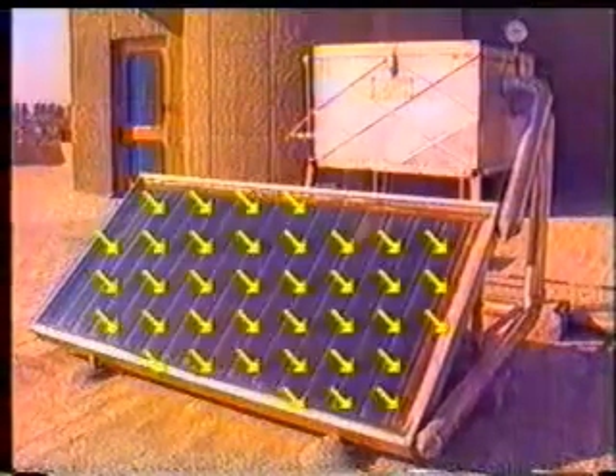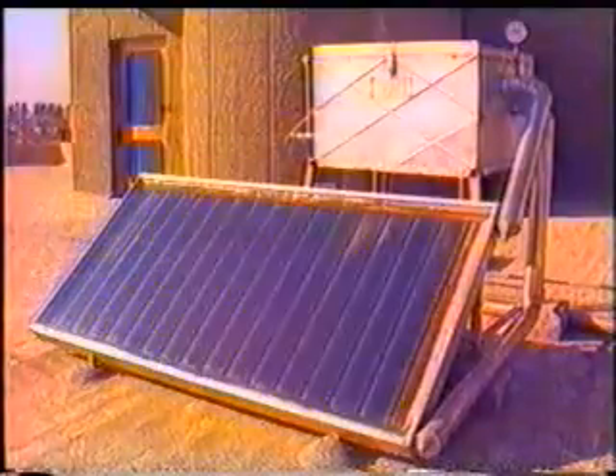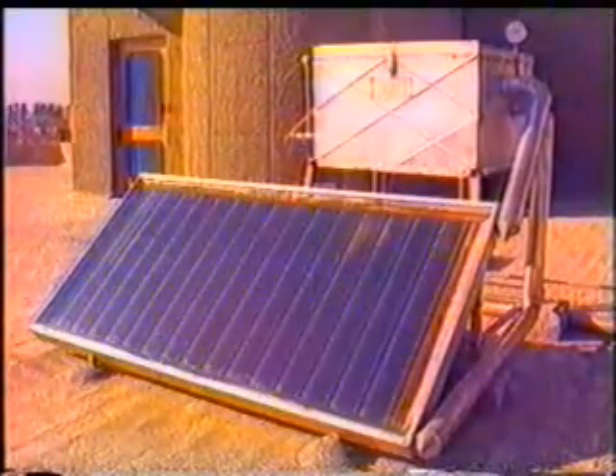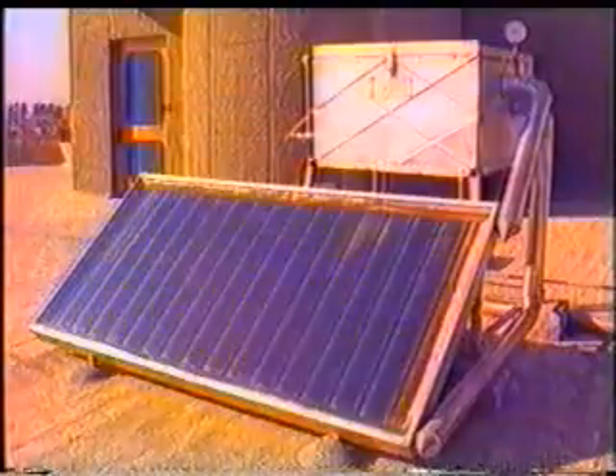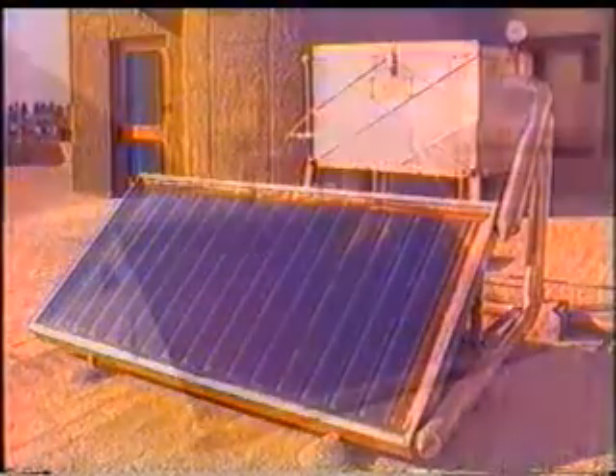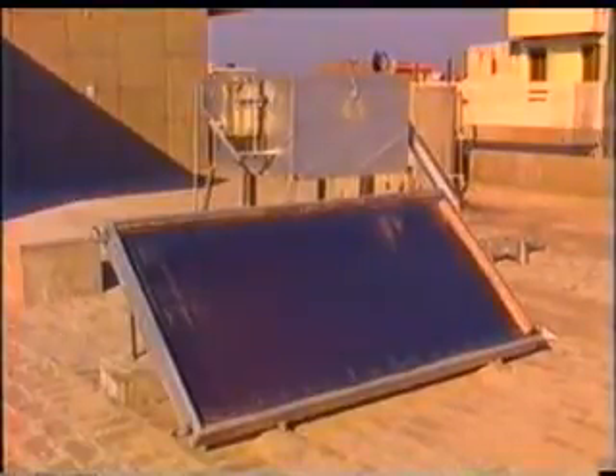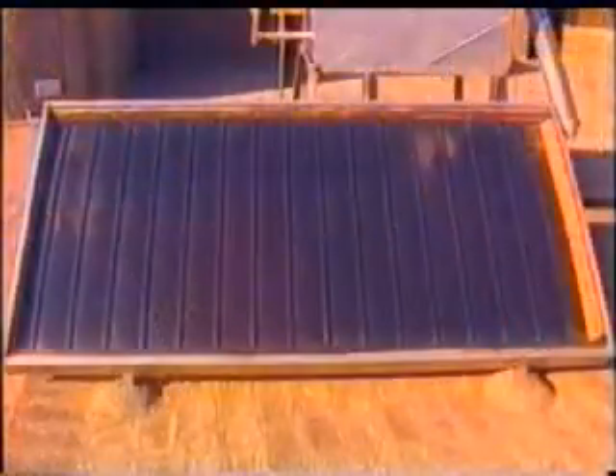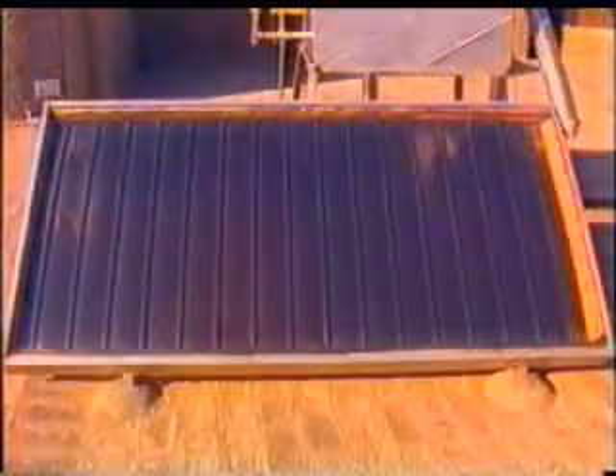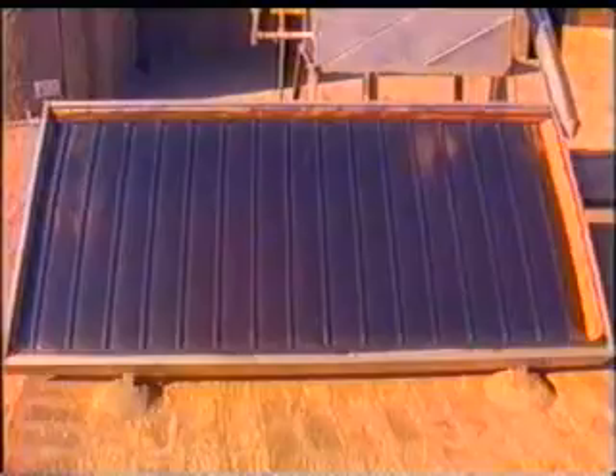For receiving the maximum solar radiation, the collectors are always kept at inclined position facing the sun. Maximum use of solar water heater is in the winter season. The inclination is kept at 15 degrees more than the latitude of the place, and it's facing the equator.